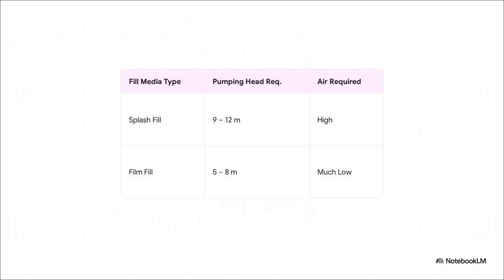Even the fill material inside the tower makes a huge difference. Older towers use something called splash fill, which basically just breaks the water into droplets. But modern film fill, which spreads the water into a super thin sheet, is way more efficient. Just look at this data: it needs less pump power and way less air to get the same job done. We're talking major energy savings.